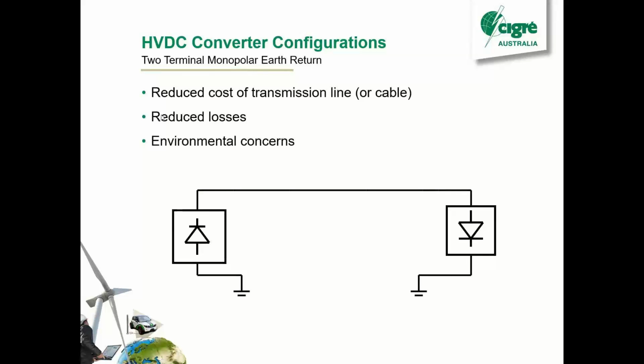It also reduces your losses because in the New Zealand example, our main transmission line is about 13 ohms between Haywards and Benmore. But if you take the earth return path, it's only about 0.5 ohms because the earth, dirt, is not a great conductor on its own, but when you've got thousands of square kilometers of it, it's actually pretty good.